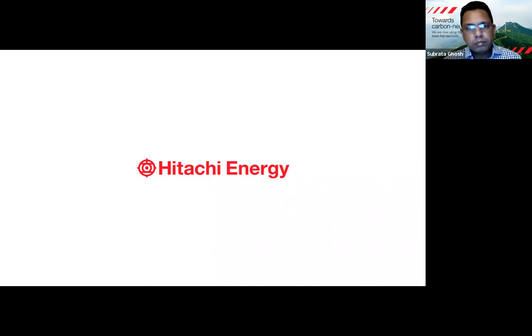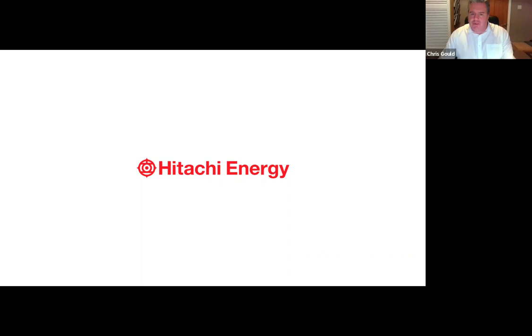Okay, thank you. If we move to Andrew Shepherd: how do the electrical operating losses compare to a conventional transformer, and what would be the anticipated life considering the semiconductors? Well, to the first question, the losses are higher than a transformer, obviously, because you have the power electronics and you have a transformer on both sides. However, on the other hand, the losses can also be reduced with an SFC with a more stable voltage. So you will have lower currents in the catenary, and this reduces the losses.